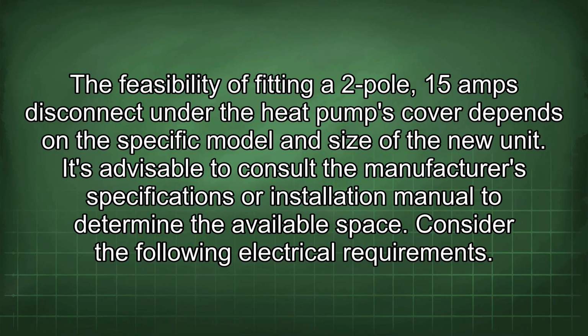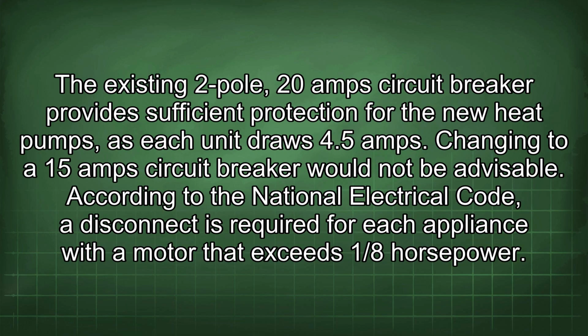The feasibility of fitting a 2-pole 15 amps disconnect under the heat pump's cover depends on the specific model and size of the new unit. It's advisable to consult the manufacturer's specifications or installation manual to determine the available space. Consider the following electrical requirements. The existing 2-pole 20 amp circuit breaker provides sufficient protection for the new heat pumps, as each unit draws 4.5 amps. Changing to a 15 amp circuit breaker would not be advisable.